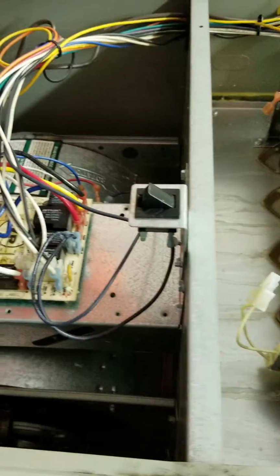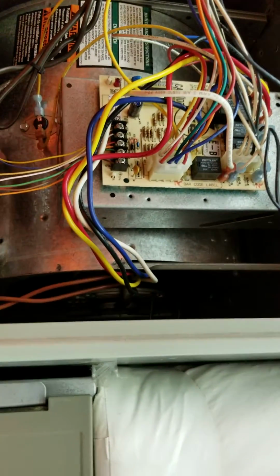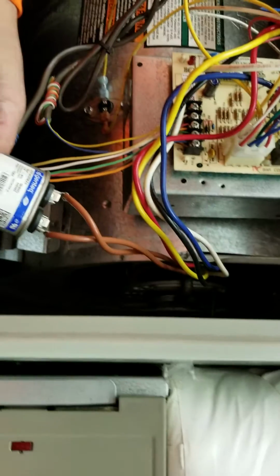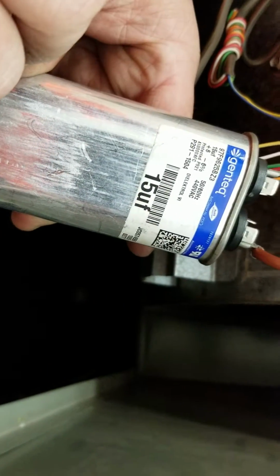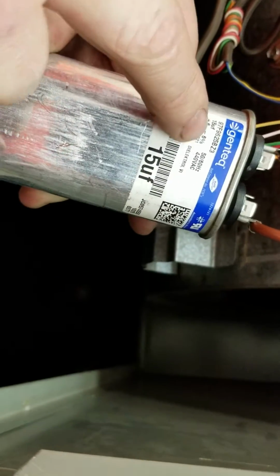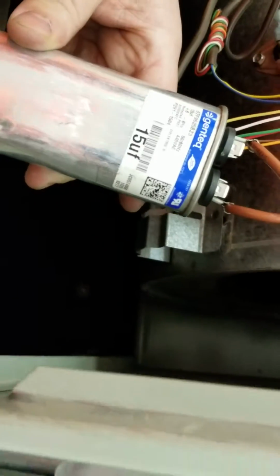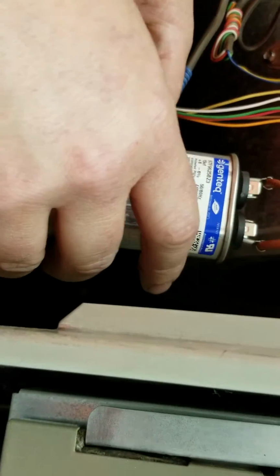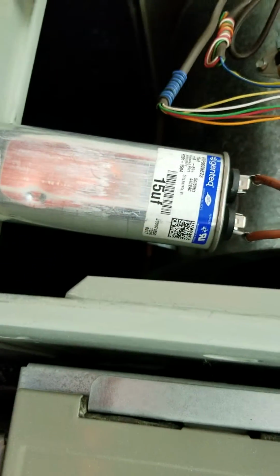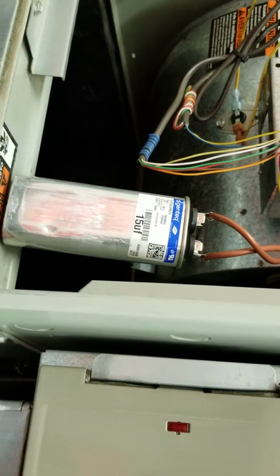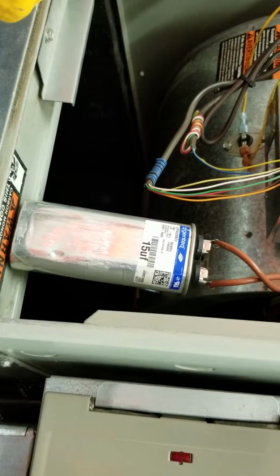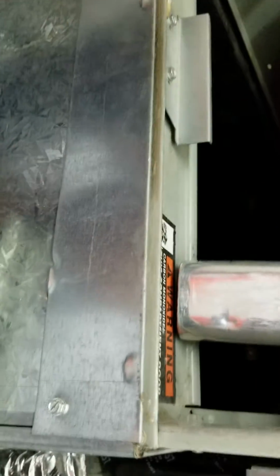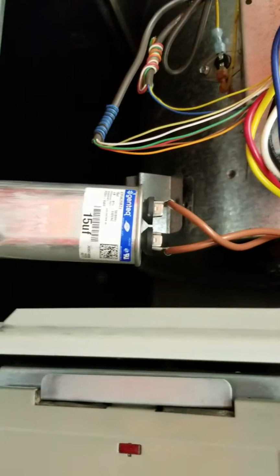So now, what we're going to do next, you'll need to check the capacitor on the blower. In this case, this one is a 15 microfarad, and it reads plus or minus 6% for tolerance. So this is why it's important to measure these. Even though it says 15 on it, next step we'll go ahead and measure it. And microfarads are on the meter. You'll want to disconnect the two wires from it.